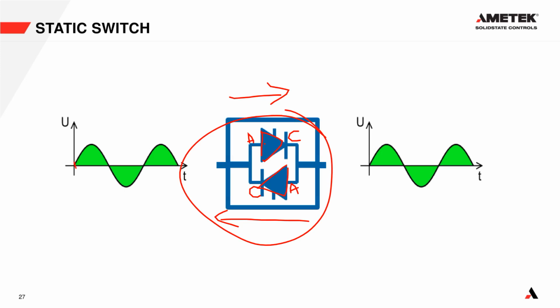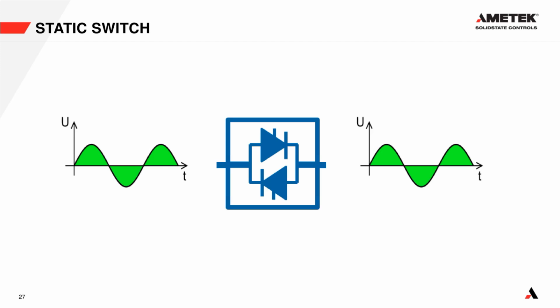So as long as we switch on the SCRs at the start of every part of the sine wave, we will get the full output here. Basically, it is just an electronic switch. If the switch is open, if we don't send a gate signal to the SCRs, the switch is open. We do have AC input on this side of the switch, but because the switch is open, you have nothing here. Then if we close that switch, the input gets through to the output.